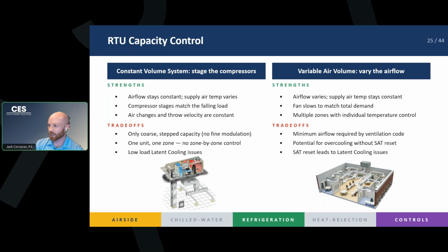And we mentioned last week and a little bit earlier, the latent cooling gets achieved with low coil temperatures. When we stage our compressors down, our coil temperature rises, and there's a risk for that coil temperature to go above our dew point, and we won't get any latent cooling. You could have a freezing cold, humid, wet space, and that's not what you want. So, you could always add in reheat and stuff, but that is a risk if you don't have that portion of the rooftop unit.